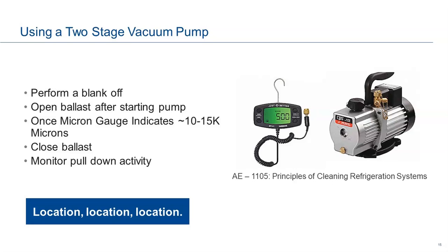So really, when you open the ballast, all you're doing is removing moisture. You're bypassing the oil and removing that moisture out into the air past the oil. It'll help you keep your oil a lot better for a lot longer time, okay?